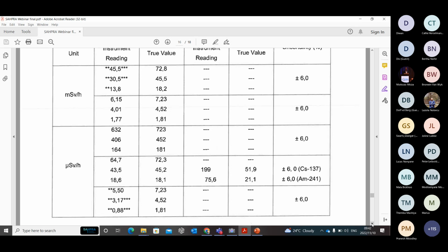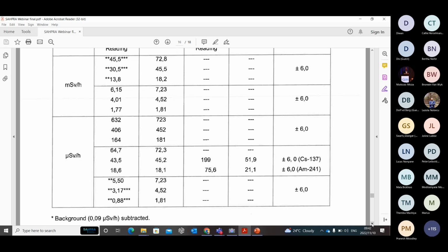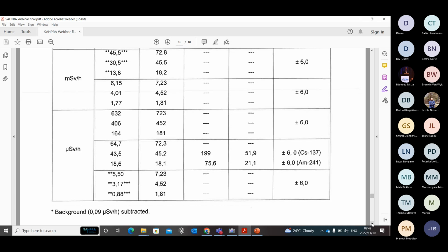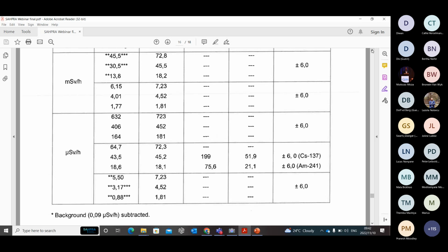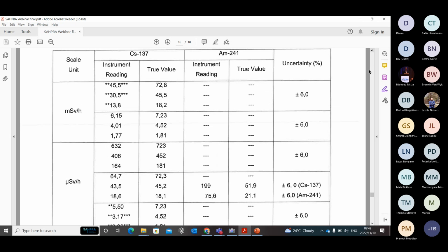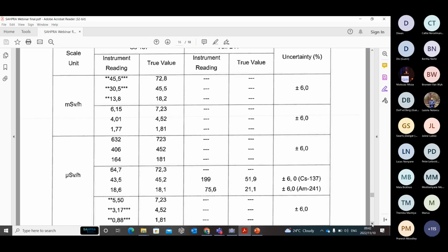If you look at these, you can see that there are 2 ranges where there is some non-compliance, which means that when we look at this instrument, the higher range of the instrument is not really performing well. And also the lower range is not performing well. So when you use the instrument, you have to be aware that at this range your instrument is not really performing well, and you will then decide whether to use it or not, depending on your requirements.